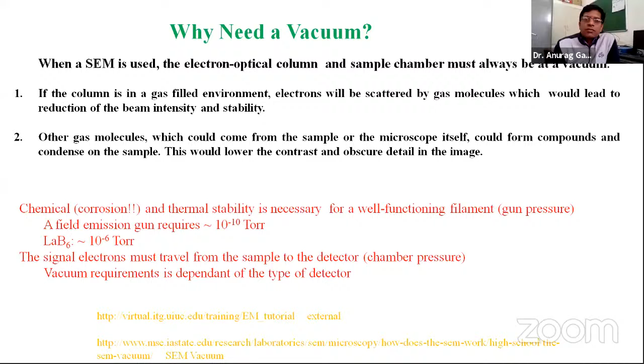The second thing is that if there are other gas molecules, they may condense on the sample as well. If they condense on the sample, naturally they will affect the contrast of your sample and also give wrong information. Some other molecules may be deposited on the surface. They are not the actual feature of your sample, but molecules from the environment present in the column. So therefore we need the vacuum, so that we can get a better, clear image from the surface of your sample. Therefore a high order of vacuum is required in these systems.